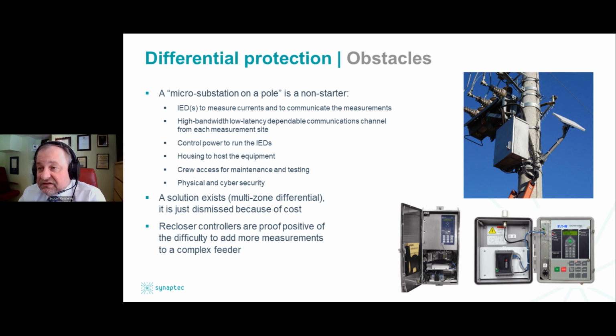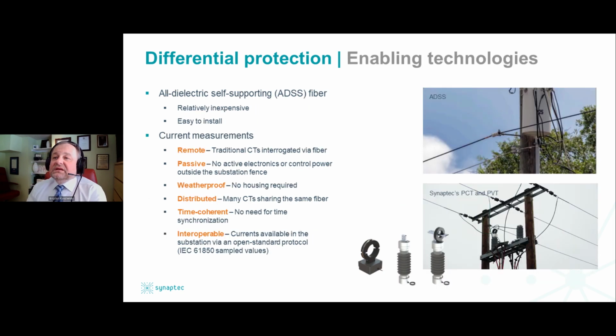And if you need to understand that, just look inside the control cabinet for a typical recloser. You will have some kind of a relay there. You will have a battery to provide backup control power. You will have a rectifier or charger to maintain that battery, some kind of radio or wireless access for controls, and so on. So before you know it, you do have a micro substation on a pole, and that's not very attractive. This, however, is changing, and there are two key enablers that allow us now to dare think about differential protection and all the other protection techniques from transmission systems in applications to distribution.